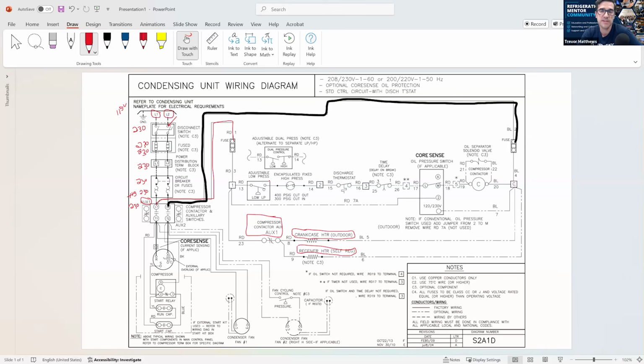When it closes that thermostat, it will send power to usually a normally closed solenoid, opening it up, sending that refrigerant through the liquid, down the liquid line, through the evaporator coil, down to the suction line as a vapor, and then that will start to raise the pressure, which will close this low pressure control, which is very important. So now we have the low pressure control. We got power coming down through here. We got it through the low pressure control, and then it goes to this encapsulated high pressure switch. It says cut out at 400, cut in at 300.